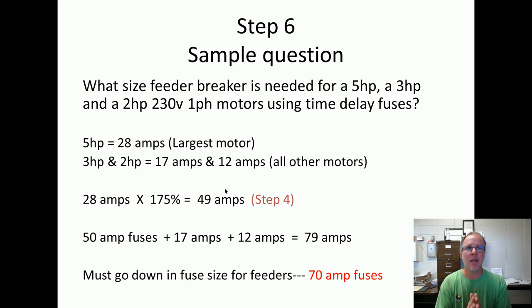I would recommend you tab your code book to step 1, step 2, or full load current, overload, breaker size, branch wire. You don't have to tab 5 and 6 because all they are is step 3 and 4, and if you can remember to add the other full load currents. So you got 4 tabs to put in there. Put a big highlighter square over the overloads, maximum, minimum, the chart for the full load currents and the breakers. That way when you turn, you've got them right there. But these ain't hard. I hope you learn them.